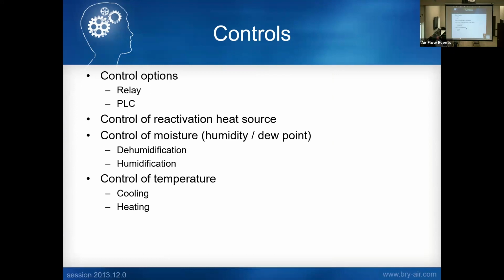So let's go over the controls of our systems. We do two different types of controls. Back in 2001 and earlier, they were all relay-based controls. After that time, we started migrating over to PLC control-based. Now everything's PLC control-based, unless you want relay logic. We do have some customers with maintenance men who have been with their companies for 50, 60 years, and that's what they want. They want the old relay logic. So we still build a few of them a year. But if you buy just a standard unit, you're going to get a PLC-based unit.